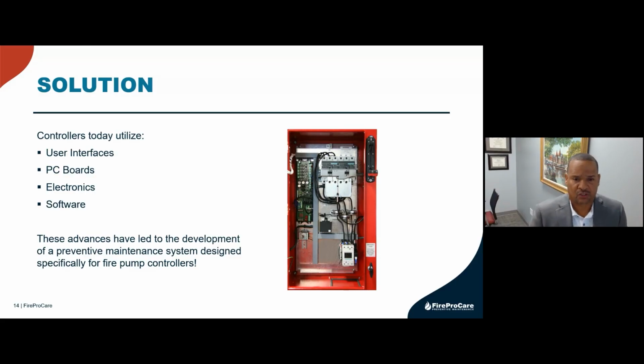So that ushered us into this new era of control panels where you had devices like interfaces, PC boards, and more electronics in the controls. That was the beginning. I remember a lot of people, we had to drag them over tooth and nail because they literally did not want to move away from relay logic, which was great. Relay logic was pretty robust. It was stable. It was easy to troubleshoot. You just follow the ladder logic, and wherever you lost voltage, that's where you backtrack to figure out what failed. Replace that component, move on, everyone's happy. And pilot lights, you don't have these LEDs, which last forever, by the way, in the newer panels. It was definitely a good era and very simple to do, but not as safe as what we have today. Today, because of the data that's been collected and the information available at your fingertips, you can perform almost everything without the need to open that door. And it's actually a safer situation as long as clients are properly using the system like they should.